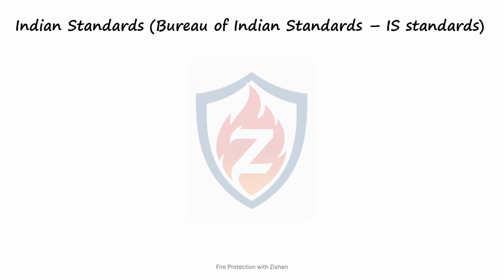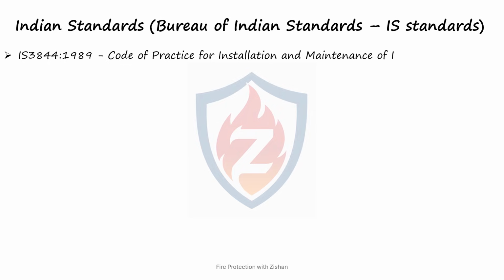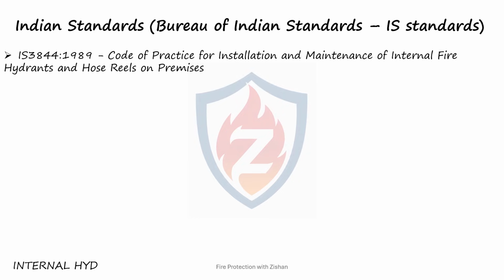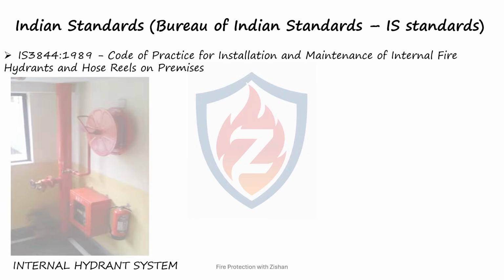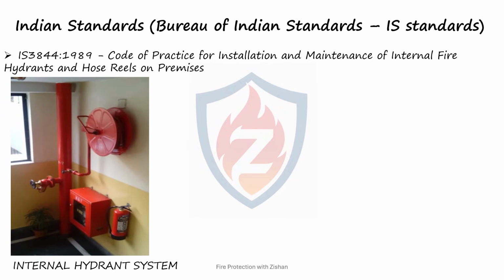Moving on to another important standard, let's discuss IS 3844:1989, which provides guidelines for the installation and maintenance of internal fire hydrant and hose reel systems within buildings. These systems are designed to provide an immediate firefighting facility for occupants and trained emergency response teams before the arrival of the fire brigade. On the left, we can see a typical internal hydrant system installation. It consists of hydrant valves, hose reels, piping, and associated firefighting equipment strategically located inside the building. These systems ensure that water is readily available at different floors and fire-prone areas during an emergency.